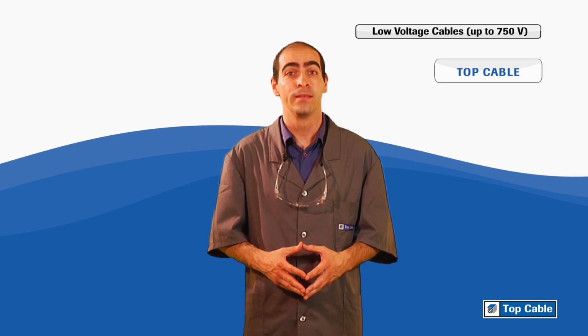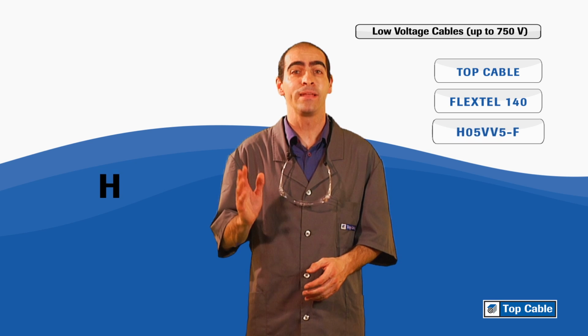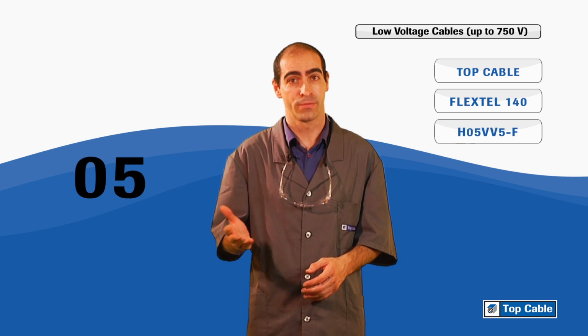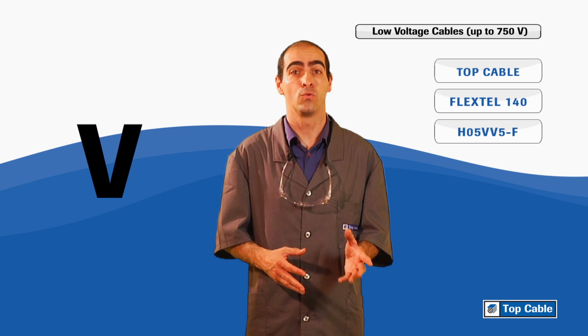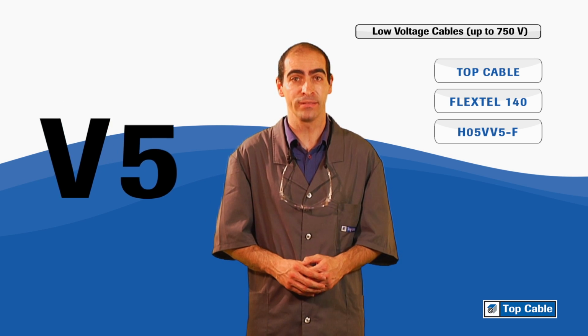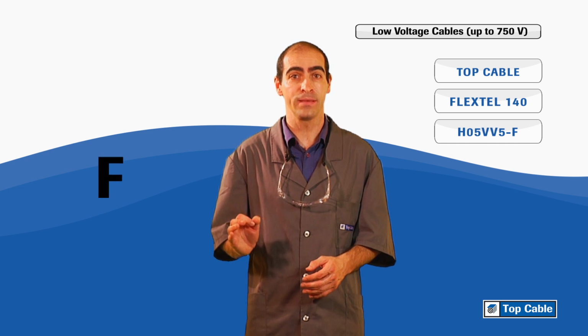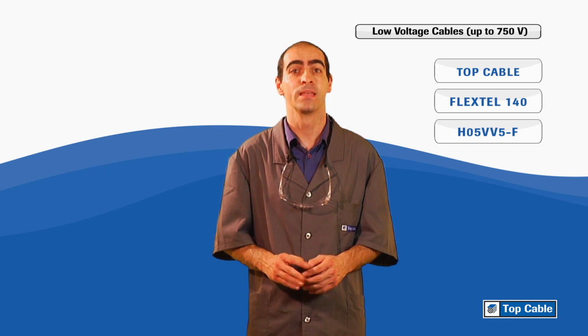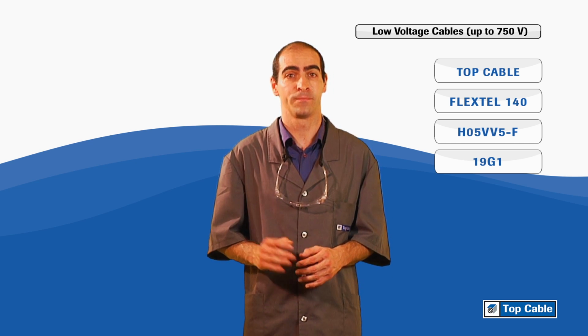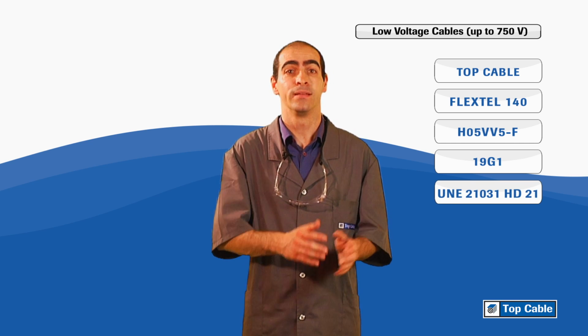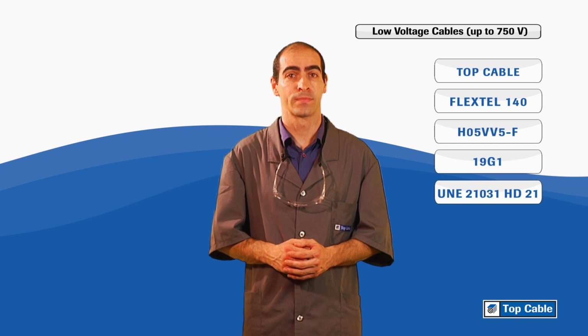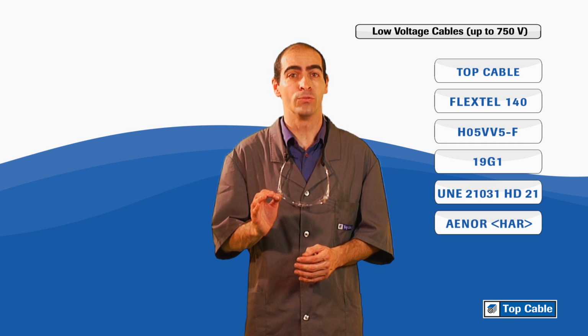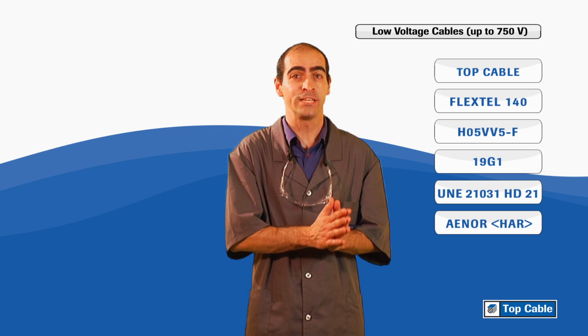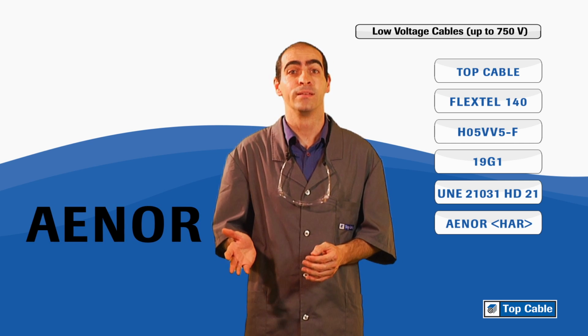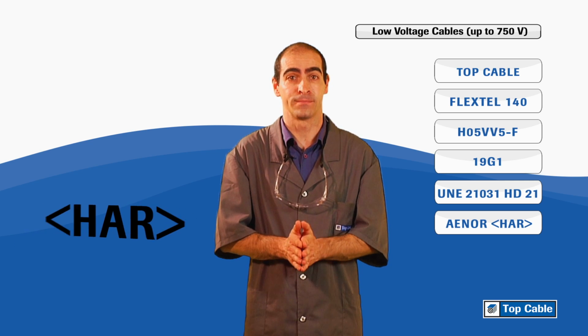Cable manufacturer. Trademark of the manufacturer. Harmonized cable, H, of 500 volts, 05. PVC insulation, V. Oil-resistant PVC sheath, V5. And flexible conductor for mobile services, F. Cable with 19 conductors of 1 millimeter squared, one of them being a yellow-green conductor. Standard for cable design, Spanish, and its correlative European. Means the product is subject to manufacturing control by an external organization, AENOR, and it is a certified product, HAR.